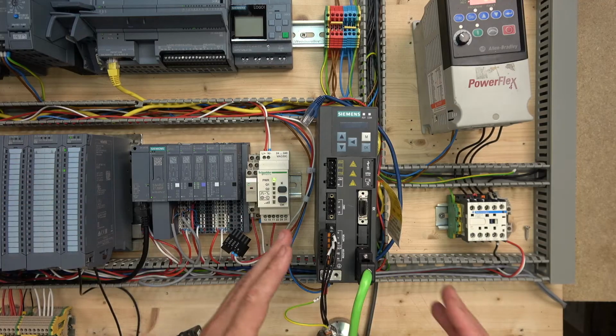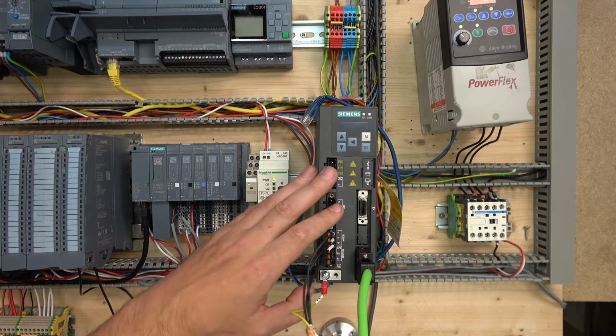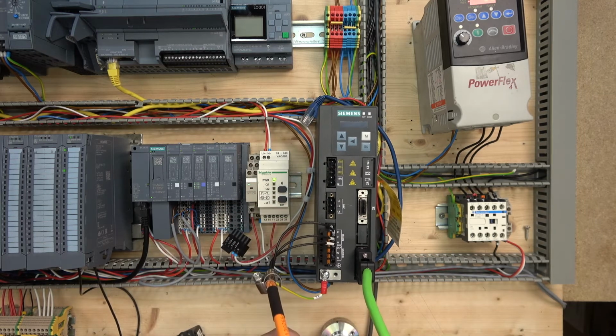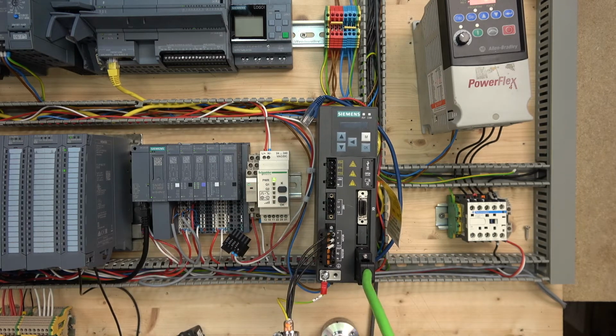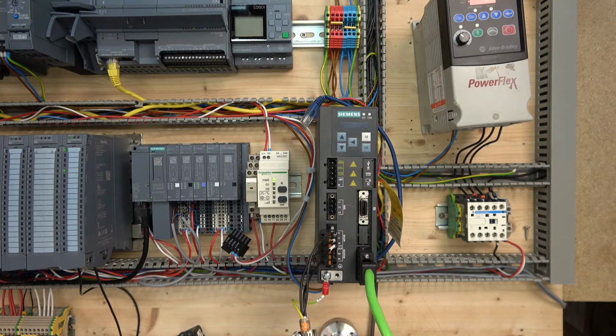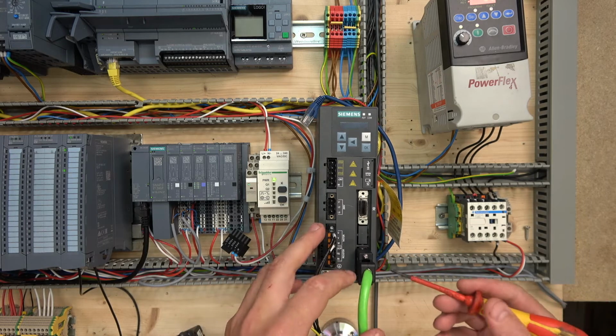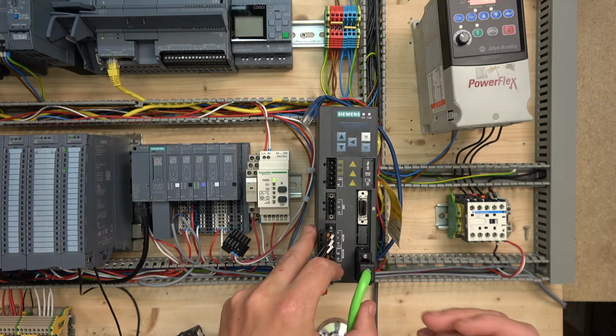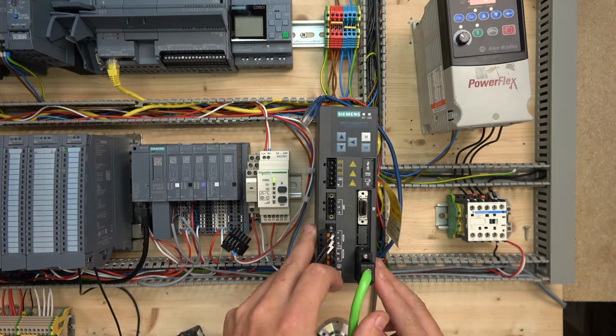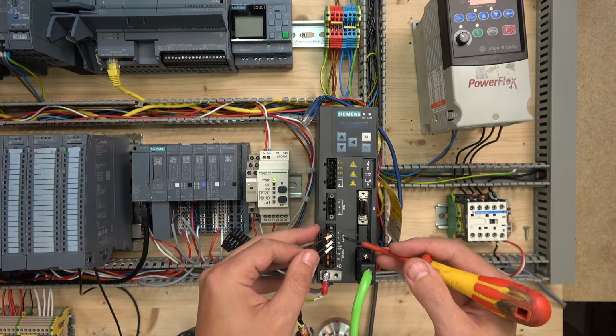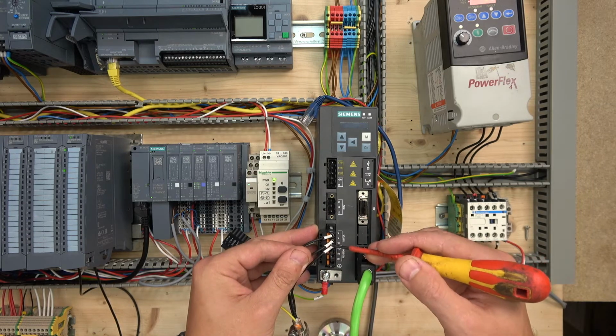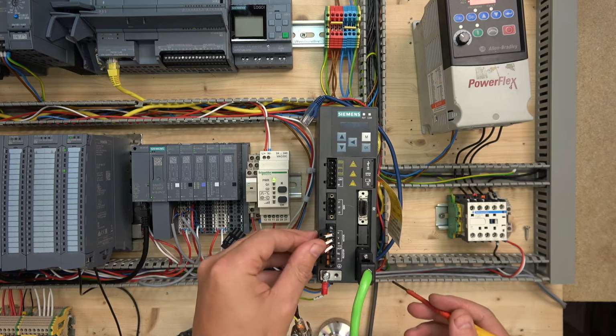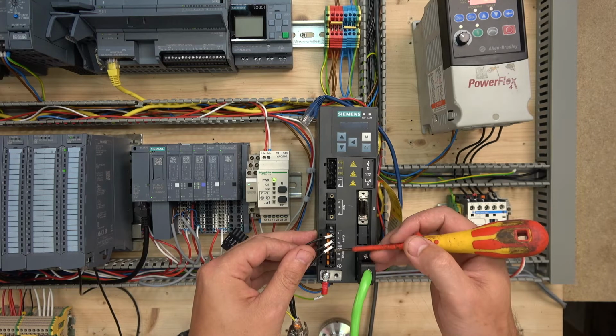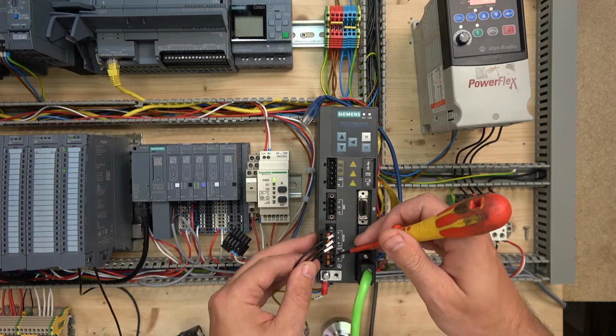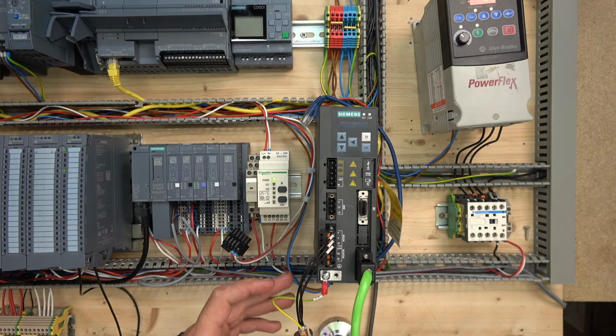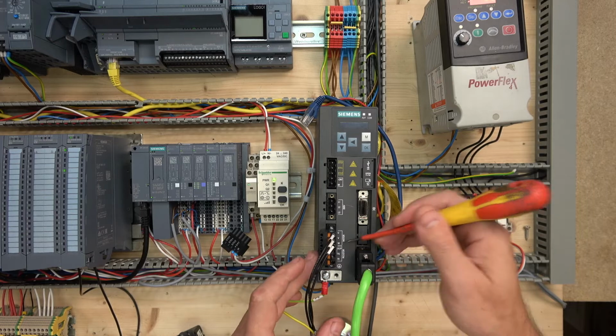So here we are. Let's start with our incoming cables that are coming from the motor. As you can see, one is orange, one is green. The green one is for the encoder, and the orange one is for the motor. The green encoder cable goes into X9, as you can see in here. The motor connection, as you can see, is UVW, and the cables themselves also say UVW, which come from the motor, so do make sure these match up. Also, you have a resistor plug in there if you have a motor that comes with a brake as well. This is where you would connect it.